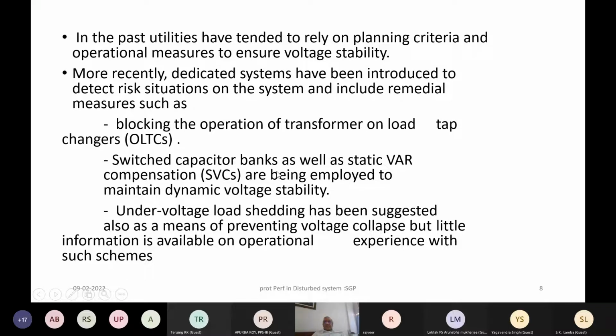Switching of the capacitor bank, static var compensators, wherever margins are available, the corrective actions can be done either manually or automatically. In certain cases, an under voltage load shedding scheme is suggested in order to prevent voltage collapse due to excessive reactive power. Basically, because of the behavior of the motor load which is there.